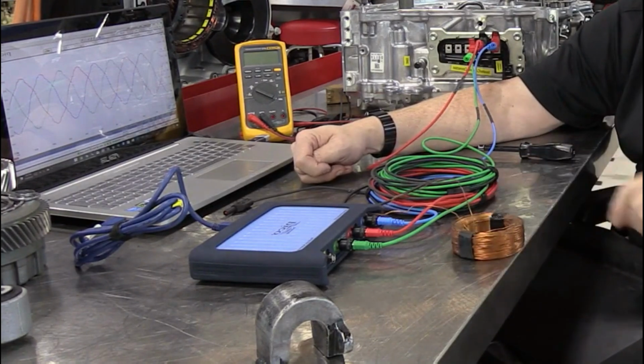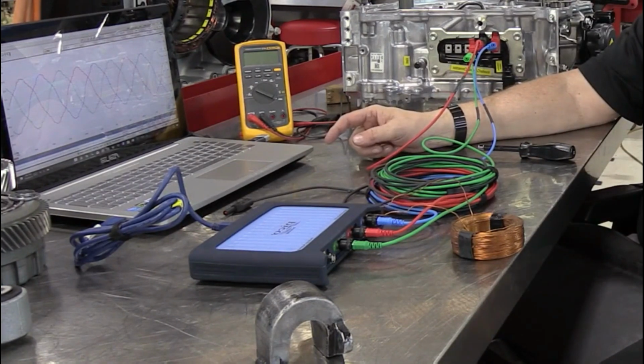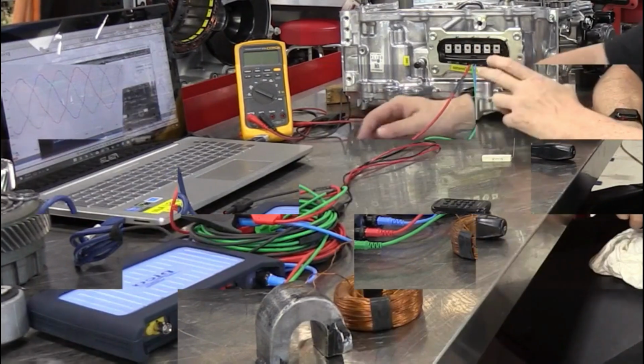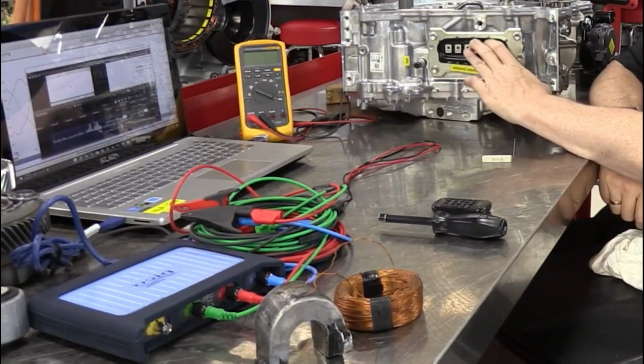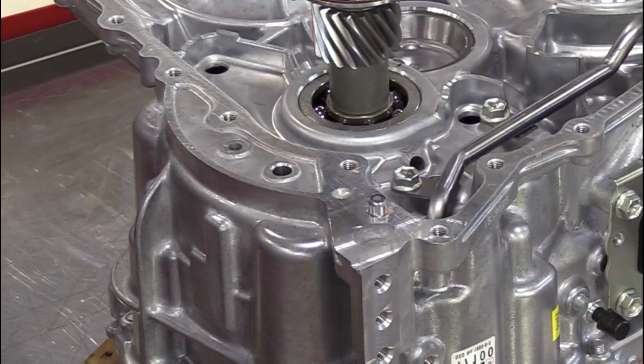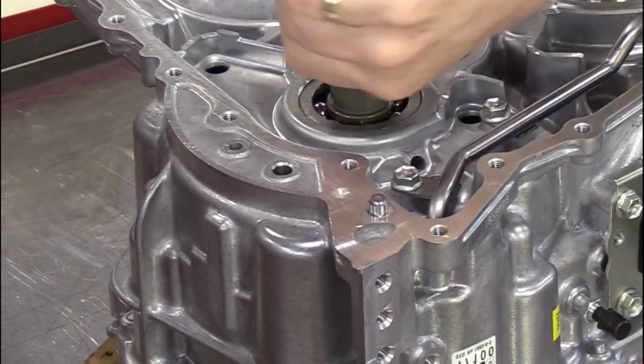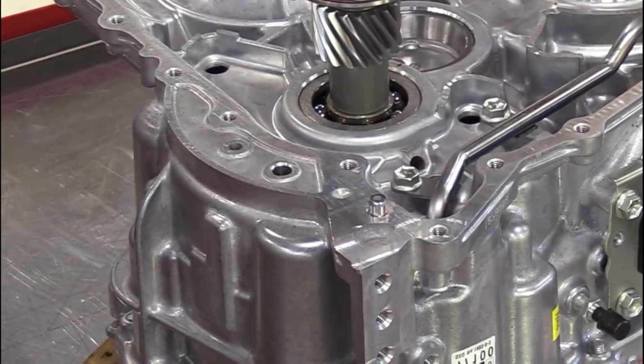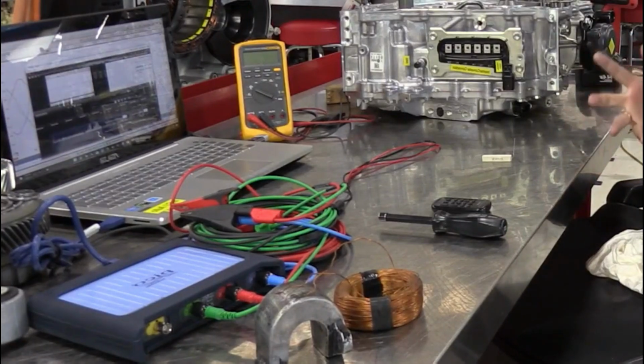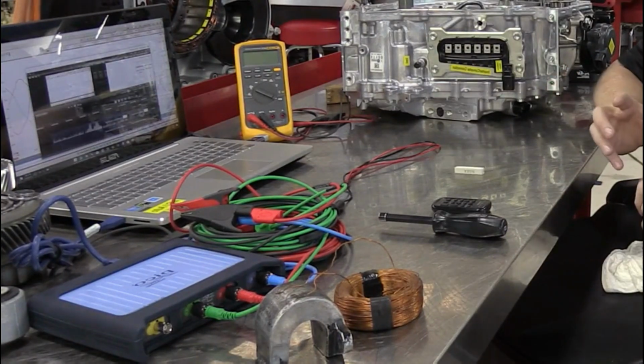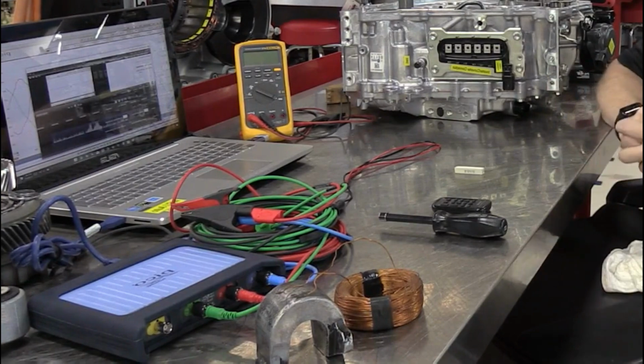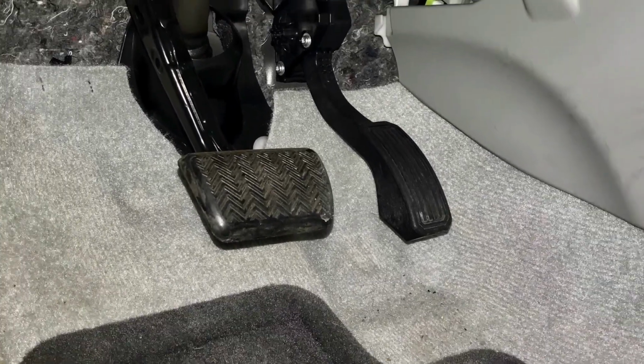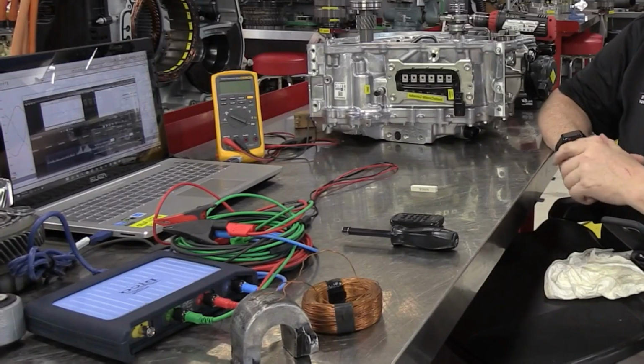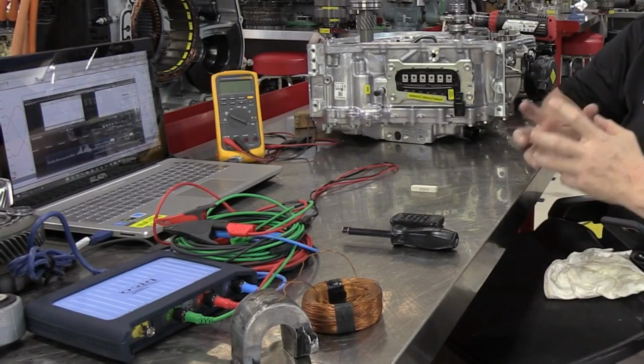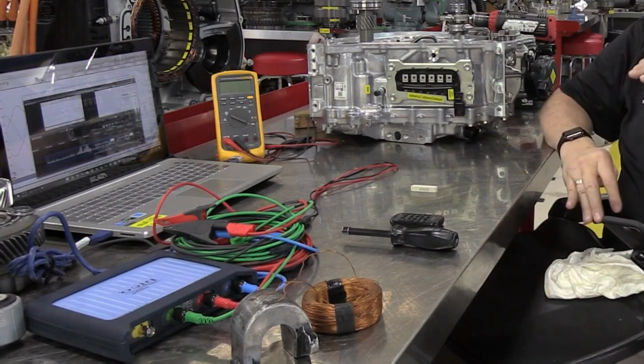Some common faults and their analysis include: open circuit can occur due to broken windings or connections. Insulation failure can cause winding short circuit leading to overheating. Motor current signature analysis can be used to detect anomalies in the stator current. Broken rotor bars can lead to uneven torque, vibration, and reduced performance.